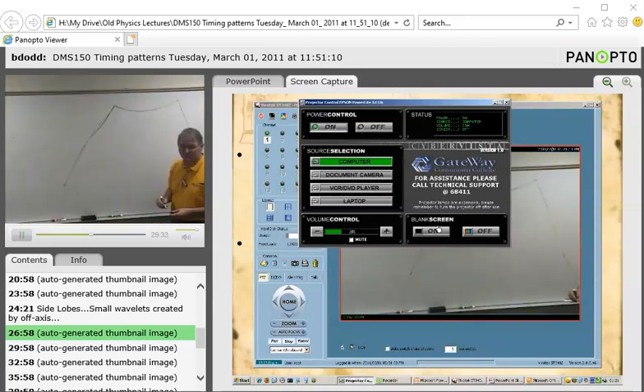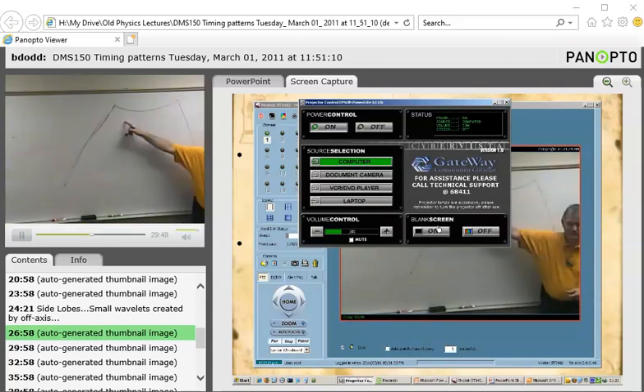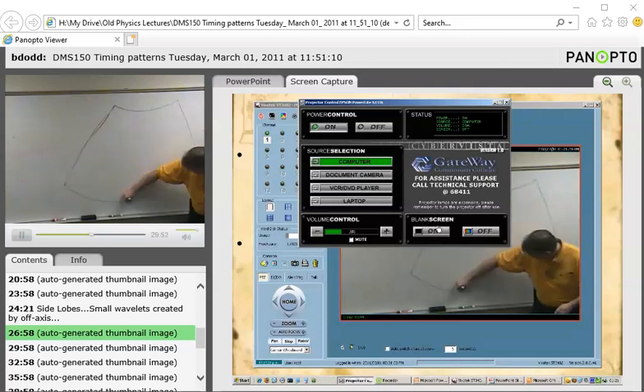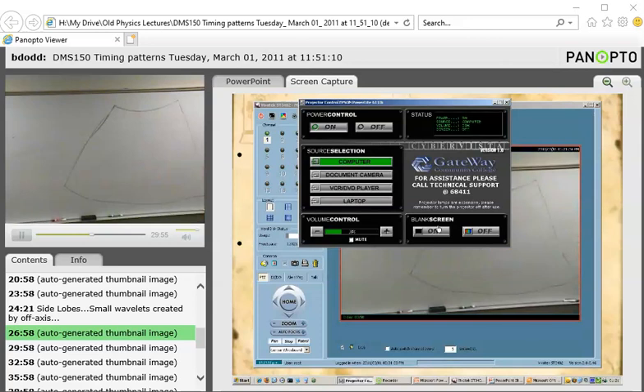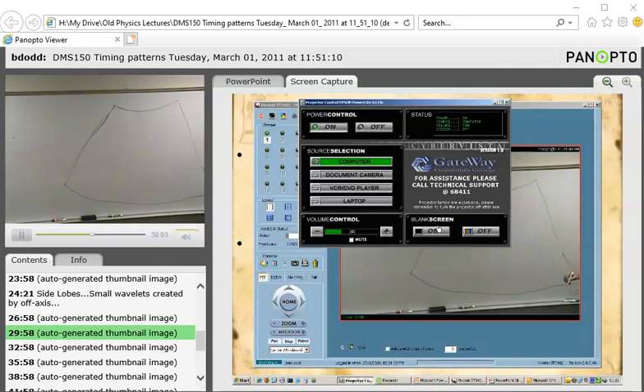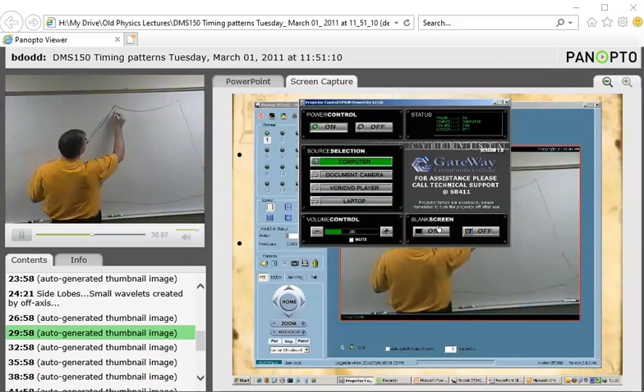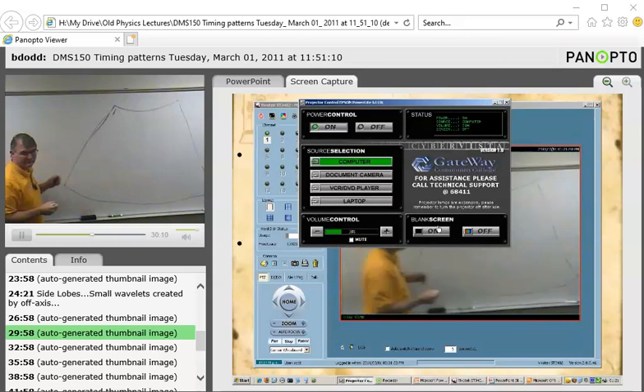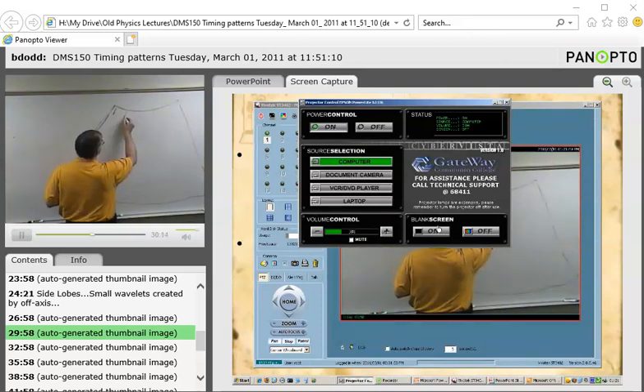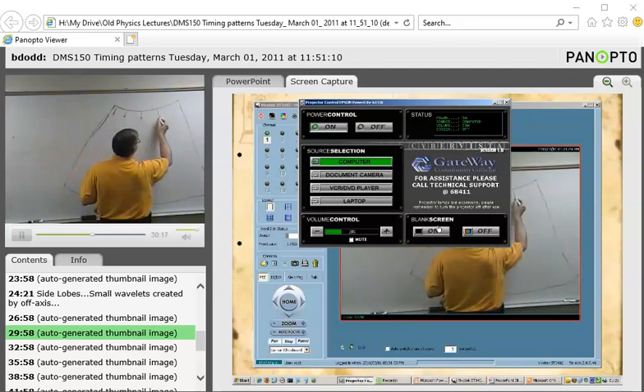And what does the far zone look like with those? Do you remember? Yeah, it diverges. Yeah, we've made it diverge. But the very bottom, is it usually flat across there? Yeah, it's the same shape, right? It just kind of is carried down. Okay. So that's your typical curved array transducer image. All right. And the beam is usually designed on these to pretty much fire straight off, perpendicular from the face of the transducer. And so that's its natural shape.